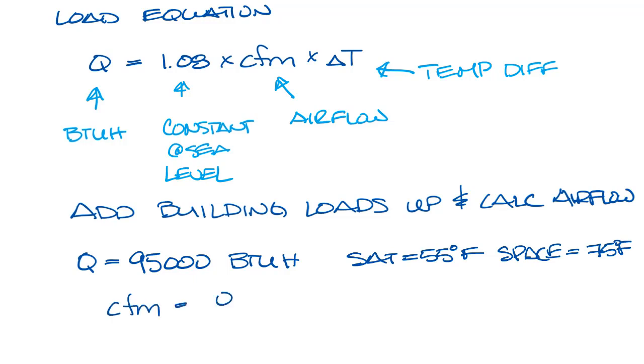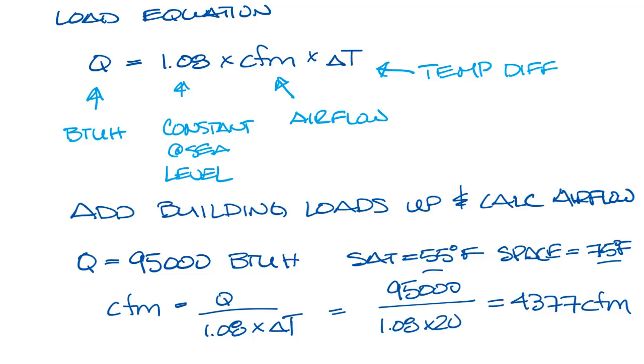So from the load equation, we know that CFM will equal Q divided by 1.08 times delta T, which is 95,000 divided by 1.08 times 20. And that comes out to 4,377 CFM. So you'd need about 4,400 CFM to handle the load of the space using 20 degree delta T air.